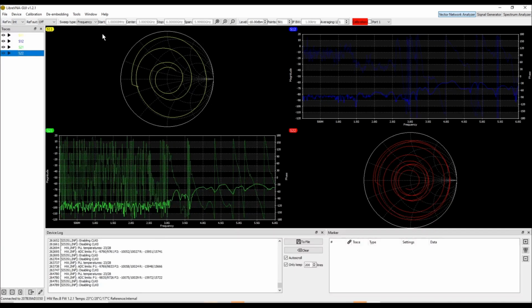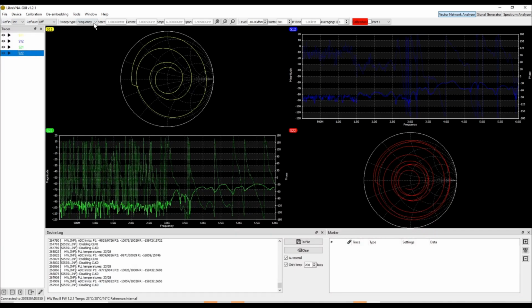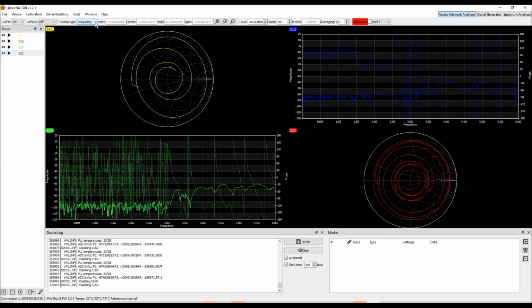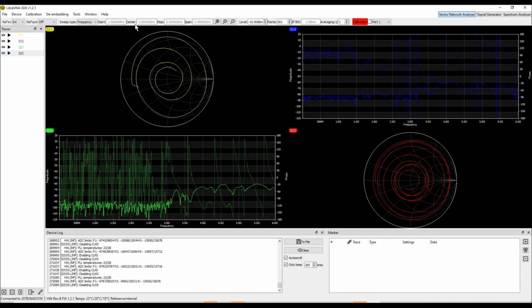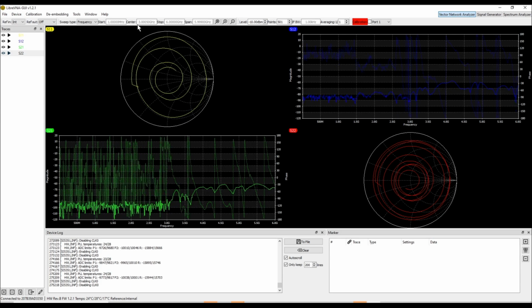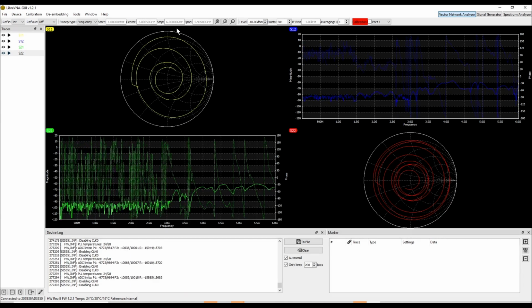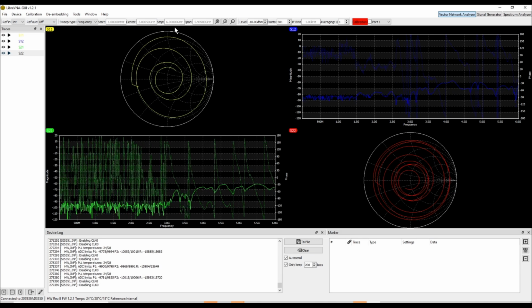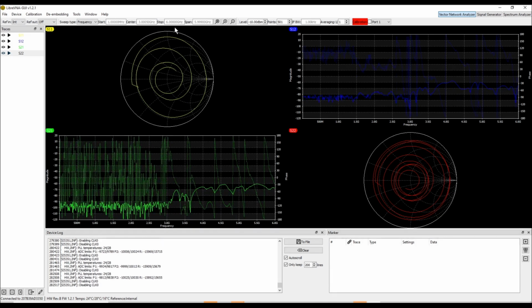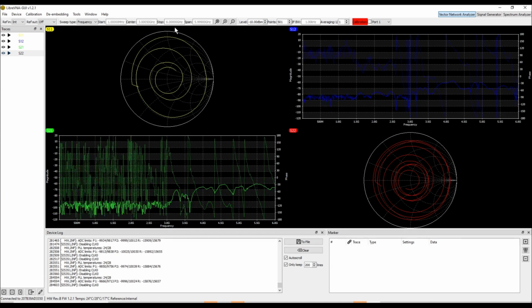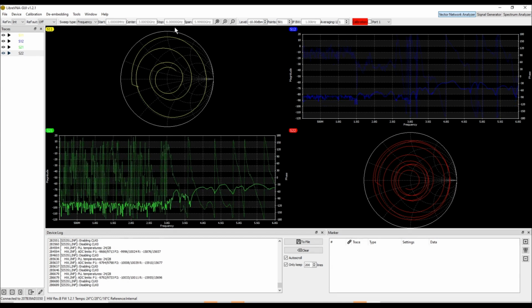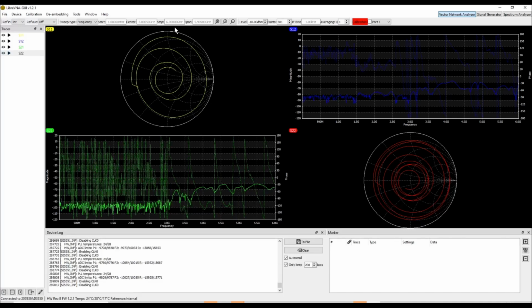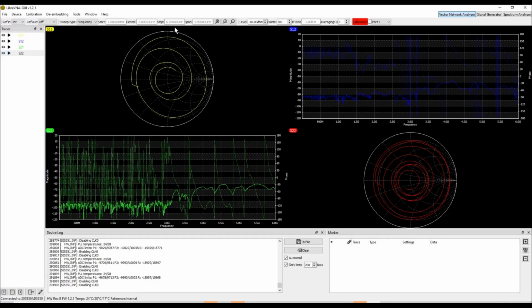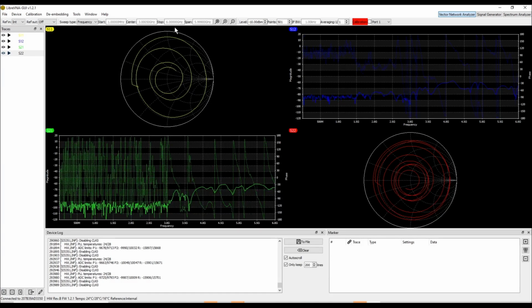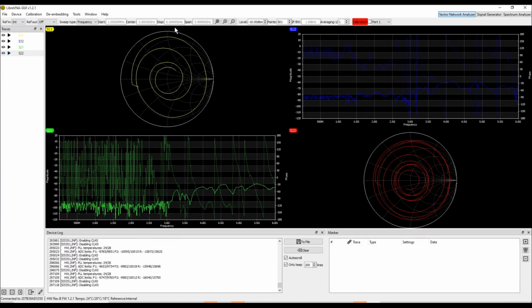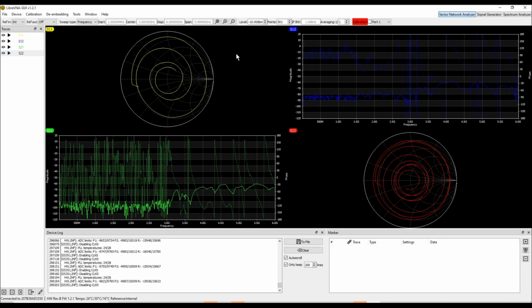If you take a look at the top of the toolbar, you'll see that our sweep type is set for frequency. You can also do power. We are starting at 1 megahertz. Center is 3 gigahertz, with a little bit of spare change left over. The stop is at 6 gigahertz, and our span is 5.999 gigahertz. I don't think that I would typically calibrate a VNA at that large of a sweep setting, based off of what I typically do with a VNA. I think I would adjust this and then create particular use case calibrations.